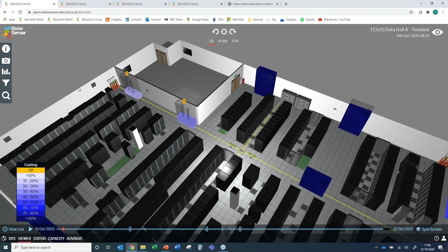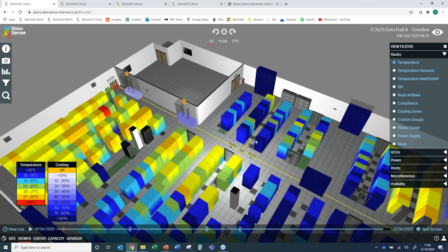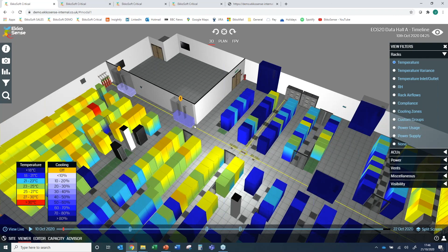So for instance, in this example, these 2 exclamation marks above the units are highlighting poor performance of those units. What that is showing you is that these units haven't failed yet, so there's no BMS failure, but our algorithms are showing us that these air conditioning units are not working as they should. And if you click on the units, it gives you more information. But I can clearly see here that what the software has picked up is that you've got some warm areas of the rooms, but these particular units have not picked up that information. They should be working harder than they actually are. So it's highlighting to the user some faults, and that could be compressor leaks, it could be spikes in compressor performance, which means the compressor is beginning to fail, or it could be stuck valves on a chilled water unit.